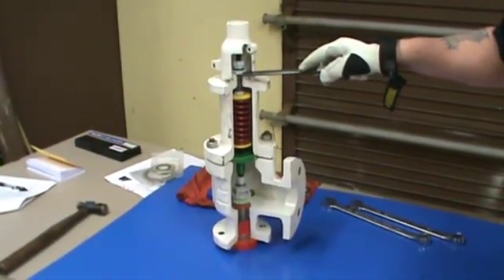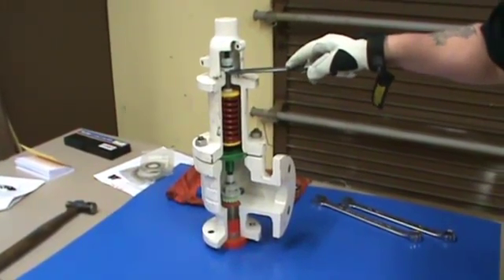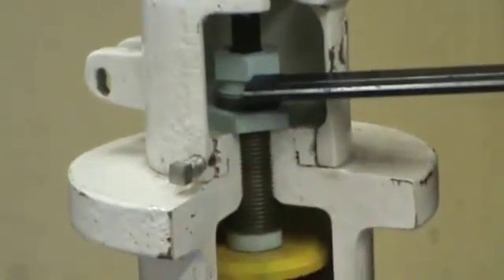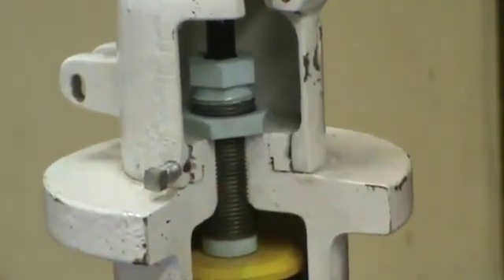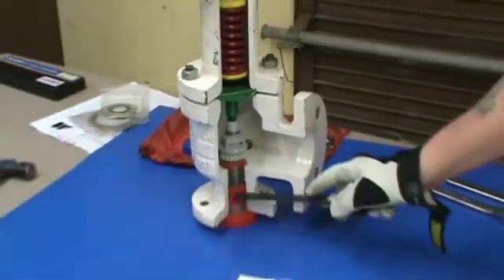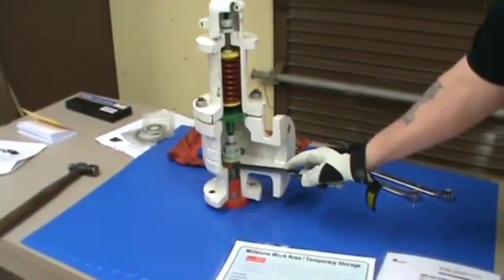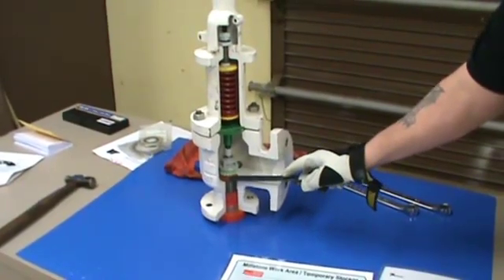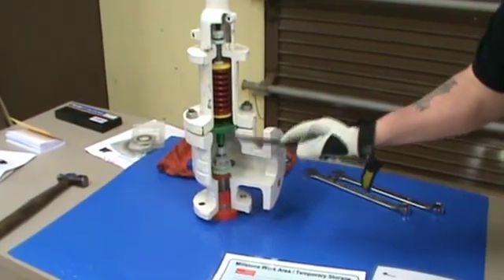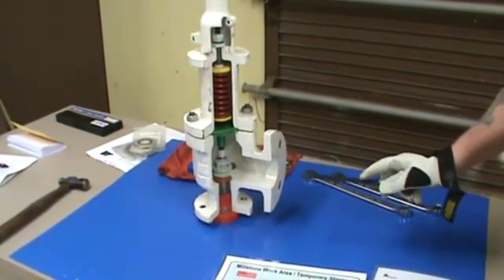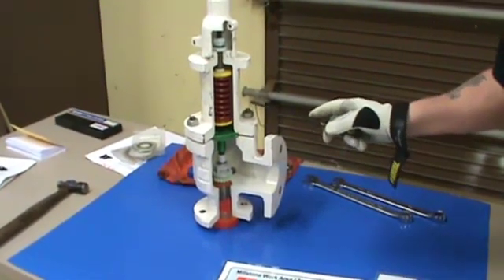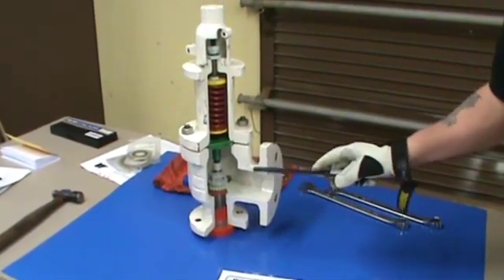The light bluish color here is a lock nut. Once you have it set, this lock nut will hold the compression screw in place. In a relief valve in the system, what happens is pressure comes up into the nozzle and builds up. Once the pressure in the system exceeds the spring pressure, this valve will lift and it will come out the discharge port allowing pressure to relieve itself and then reseat once pressure is back to normal.